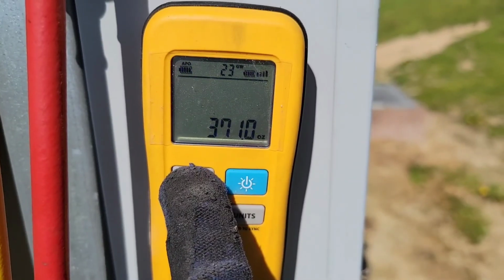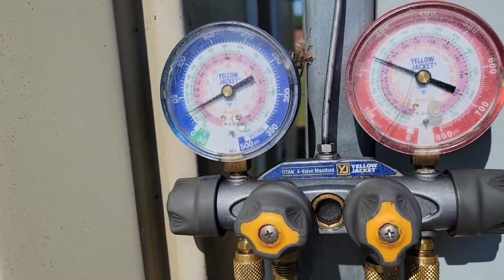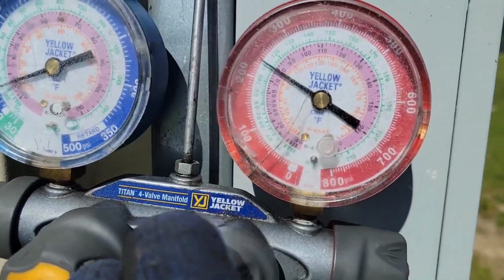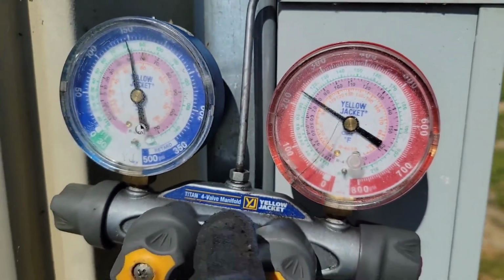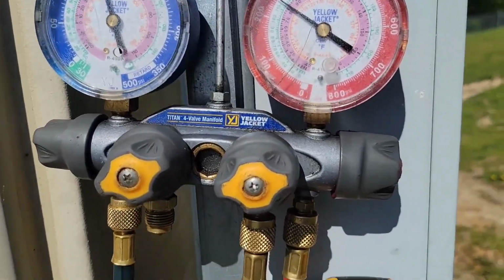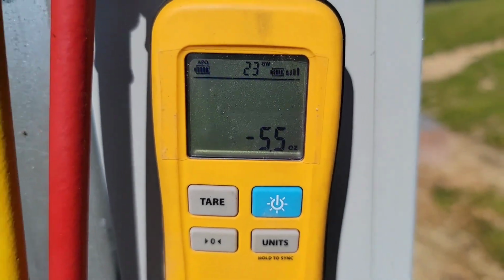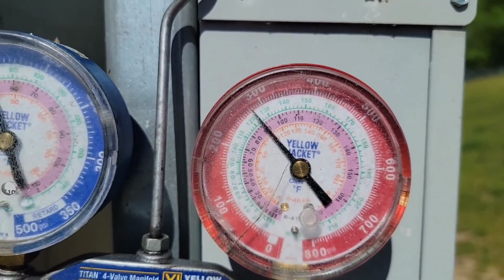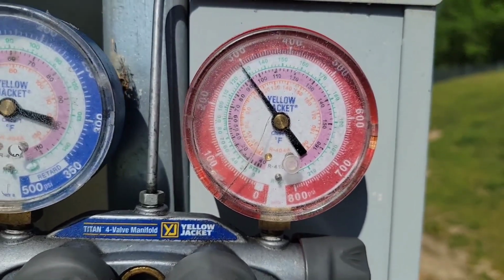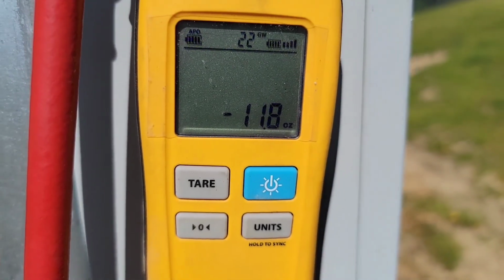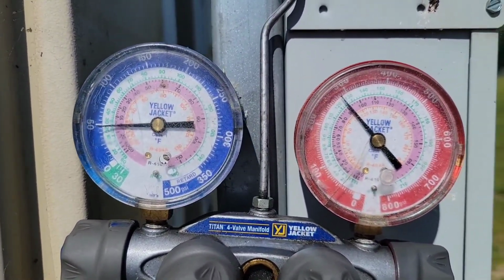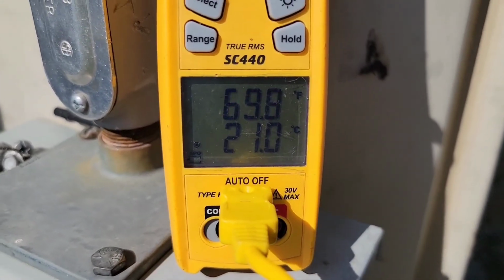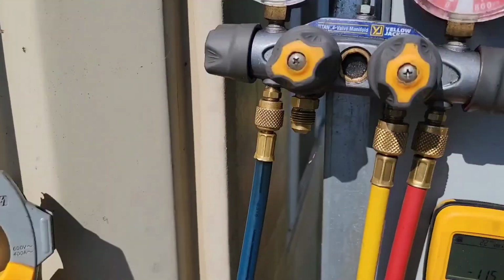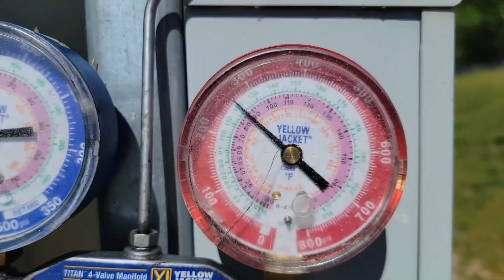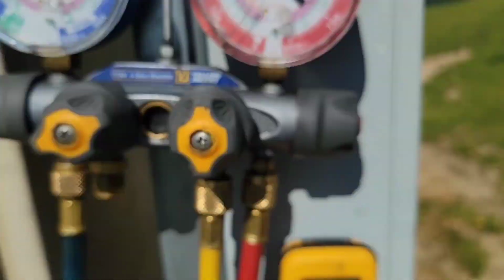Oh, unit just kicked back on. Zero out the scales, already bled the line. We're gonna add some refrigerant. It's 25 and 225. Sure that's closed. We got 5 ounces already. Ooh, our head pressure is climbing. I'm gonna go ahead and shut this down. It's about 12 ounces right now. Suction line temperature 70, 69. Ooh, that is not good. Still need some more refrigerant. 45 and 265. Oh yeah, we definitely need some more. So we're gonna add some more refrigerant.